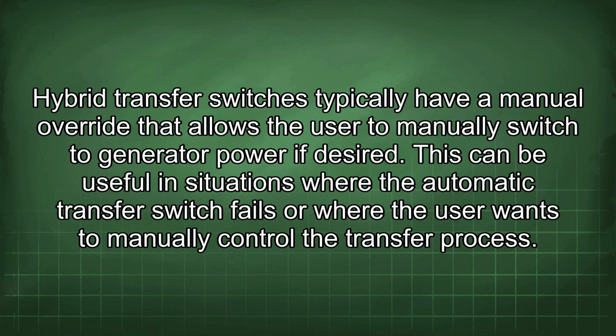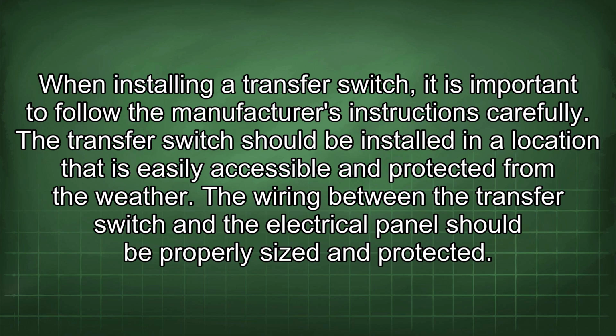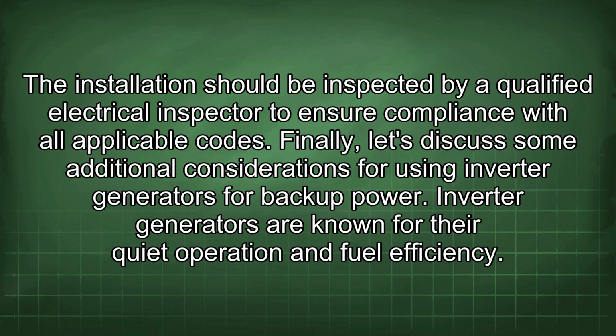When installing a transfer switch, it is important to follow the manufacturer's instructions carefully. The transfer switch should be installed in a location that is easily accessible and protected from the weather. The wiring between the transfer switch and the electrical panel should be properly sized and protected. The installation should be inspected by a qualified electrical inspector to ensure compliance with all applicable codes.